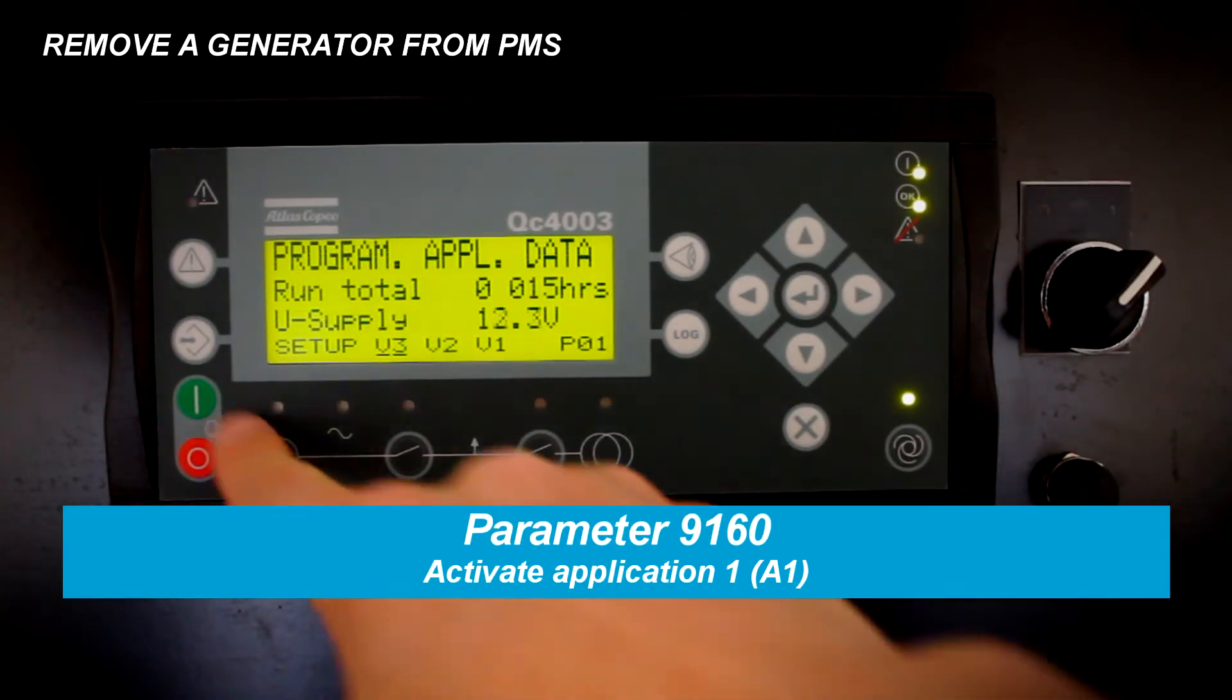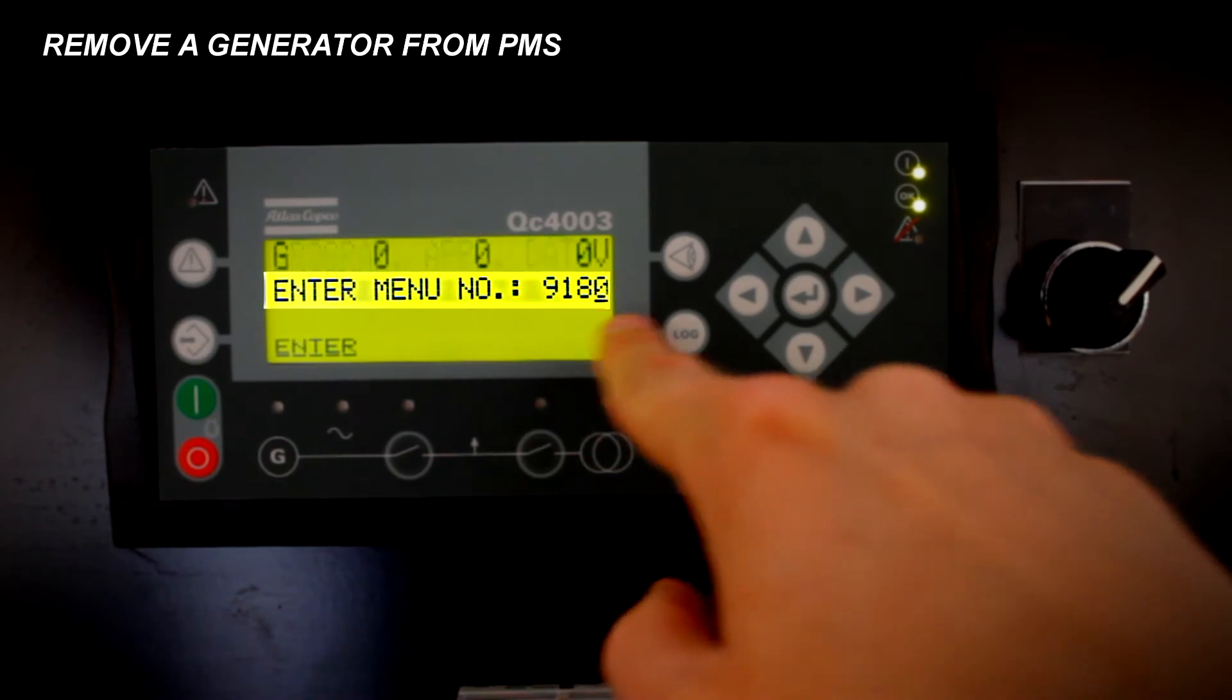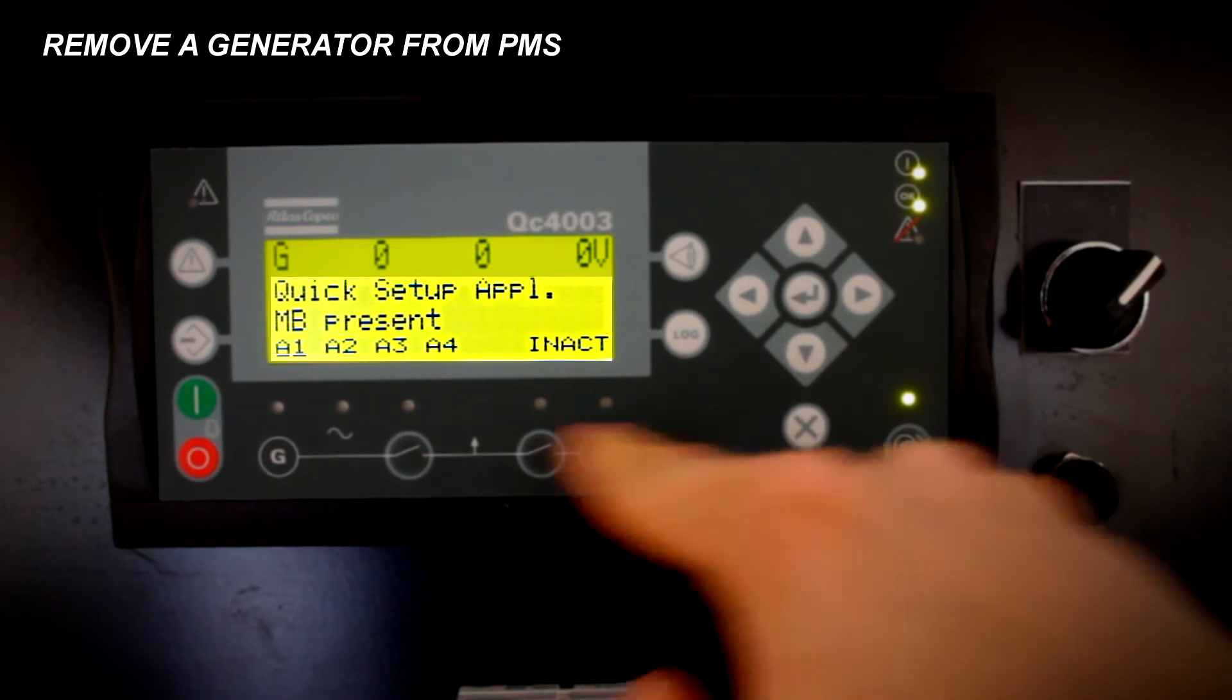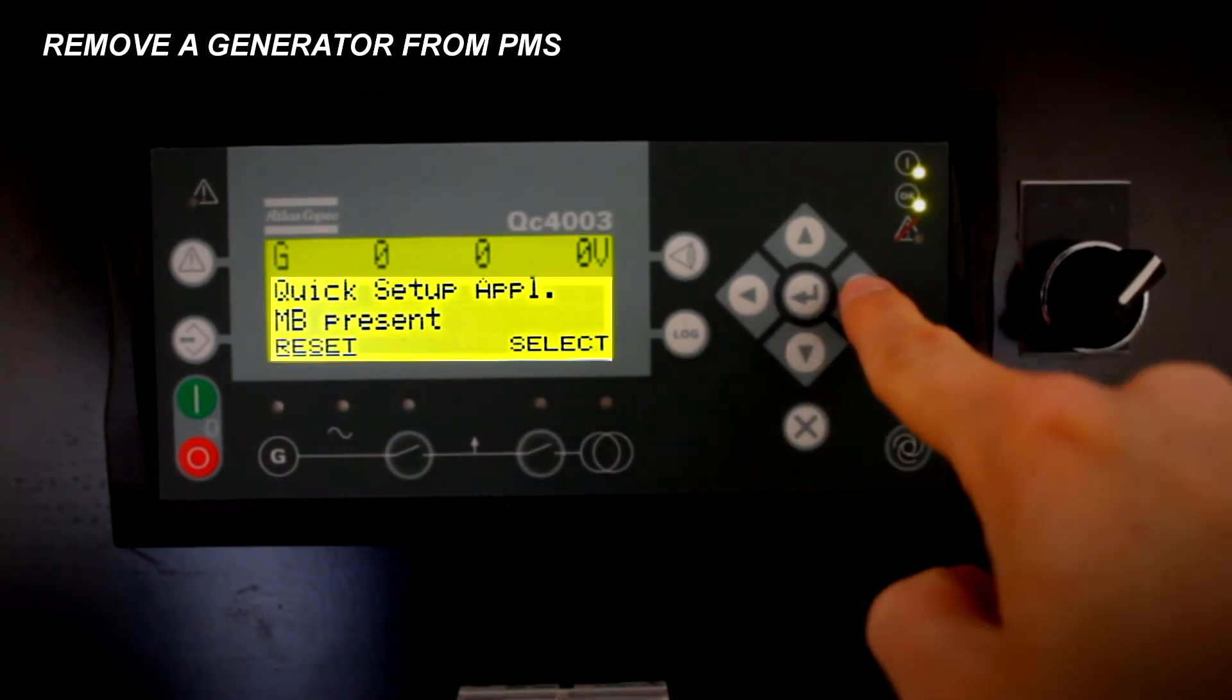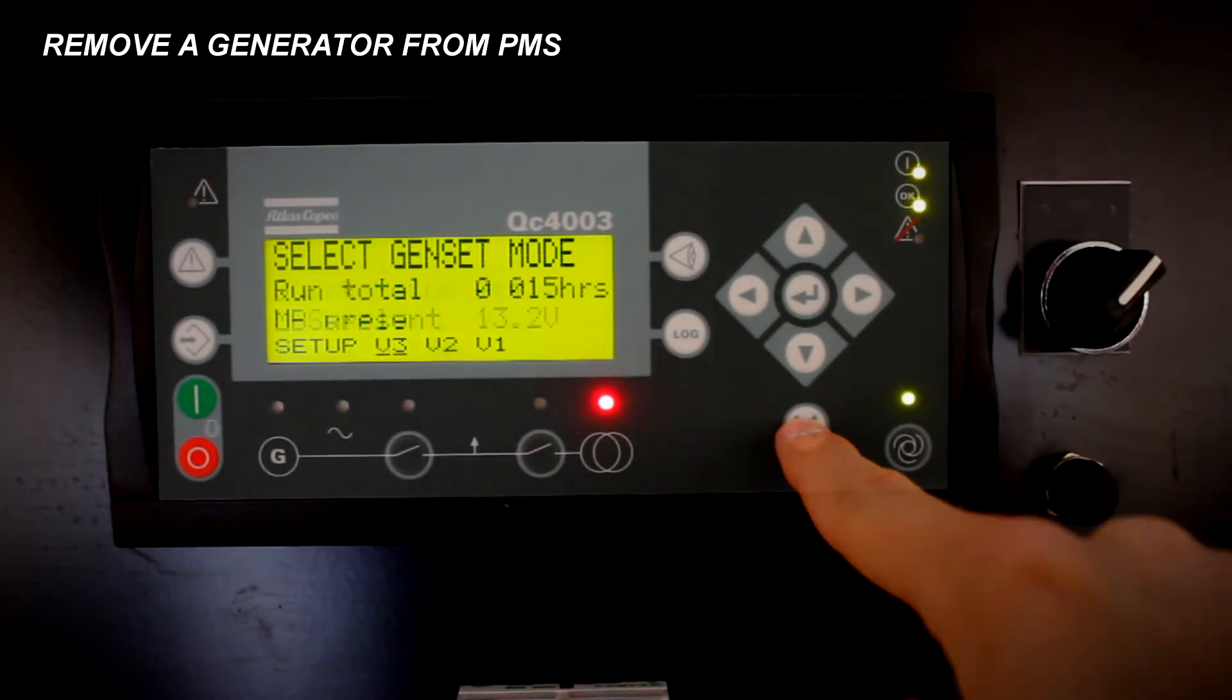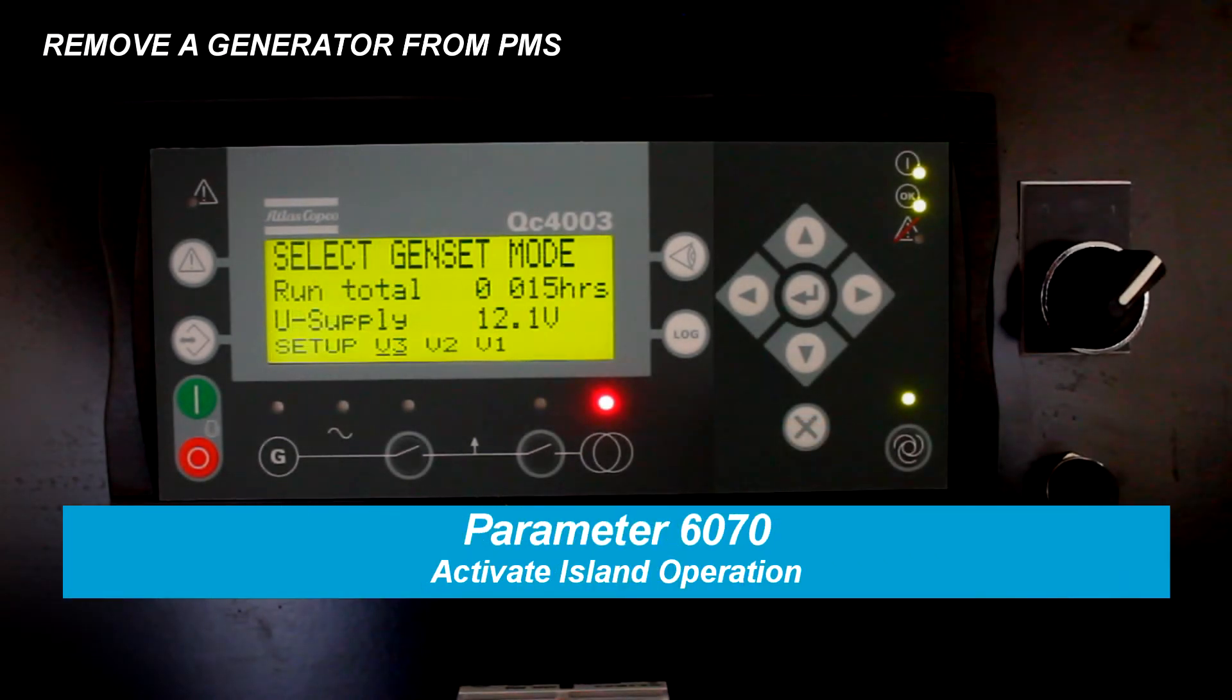Put the controller as application 1 by pressing the jump button and find parameter 9160. Activate application 1 at parameter 9160. Activate island operation at parameter 6070.